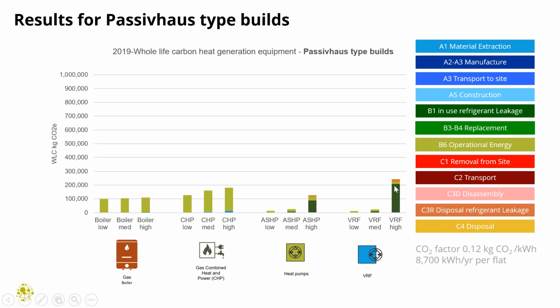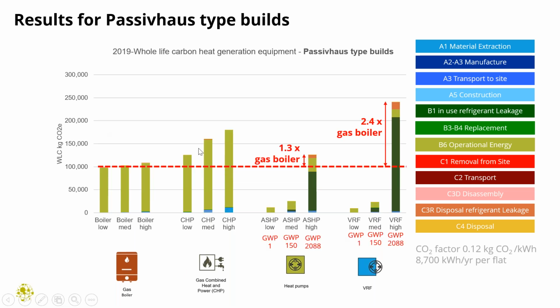You cannot see really well, but you see VRF in a high impact scenario as a heat pump might be bigger than a boiler and a CHP. So for this slide, I actually zoomed in, and you can see that air source heat pump using a high global warming potential refrigerant of 2088, which is very common, it's typically R410A, can be higher than a gas boiler, and same for VRF, but even bigger.